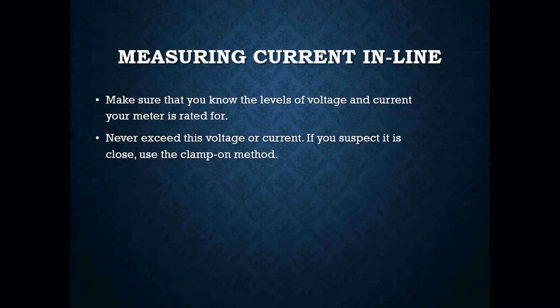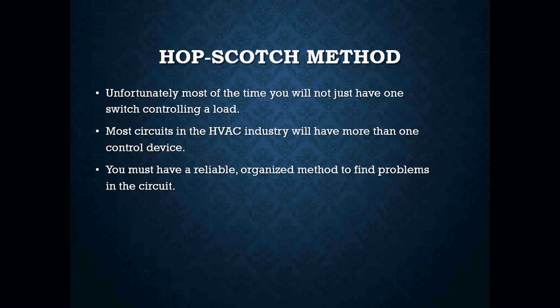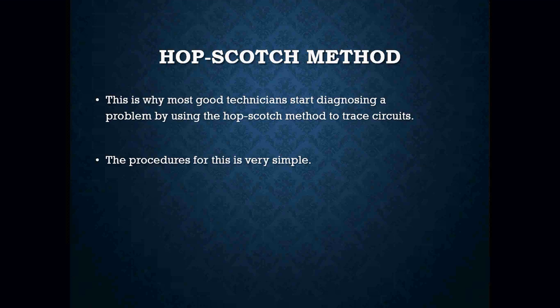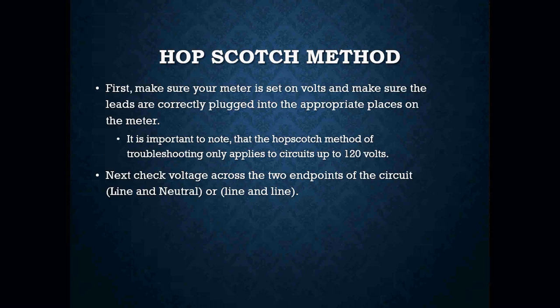Okay, make sure you know the levels of voltage and current your meter is rated for, and never exceed the voltage or current. If you suspect it is close, use a clamp-on meter. Unfortunately, most of the time you will not just have one switch that's controlling a load. You may have multiple switches that control a load. Like in most HVAC industries, you're going to have a lot of control devices. So you must have a reliable and organized method of troubleshooting these types of circuits, and that's known as the hopscotch method. This is why most good technicians start diagnosing a problem using the hopscotch method to trace out their circuits. Okay, and this procedure is relatively simple.